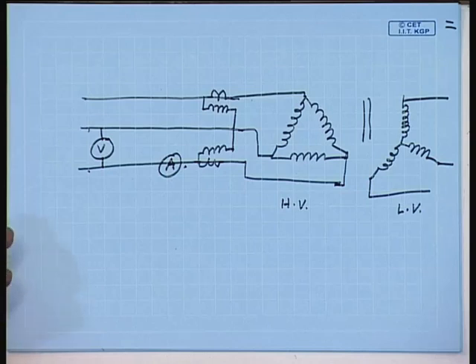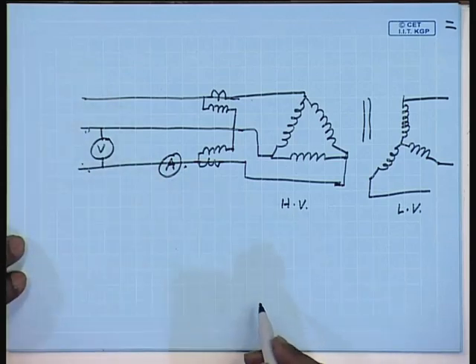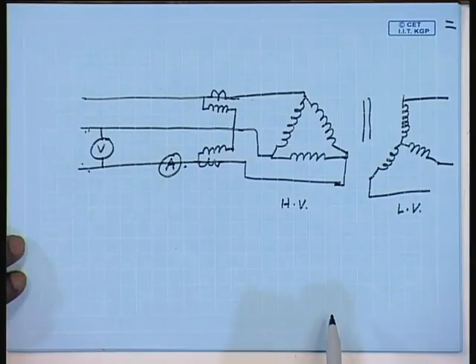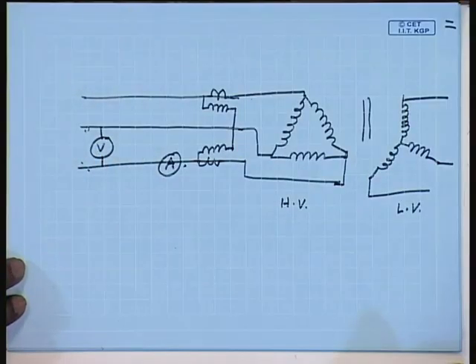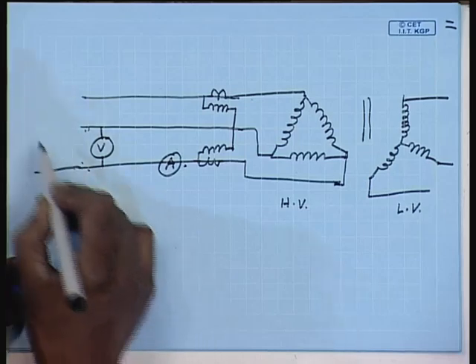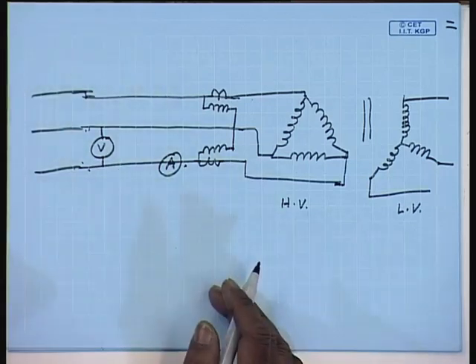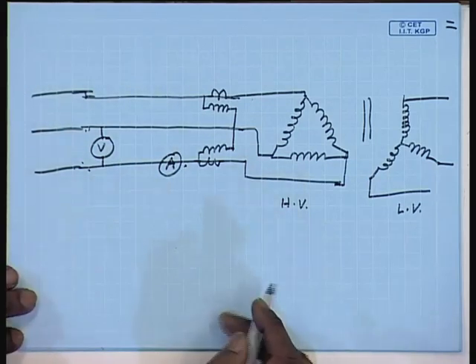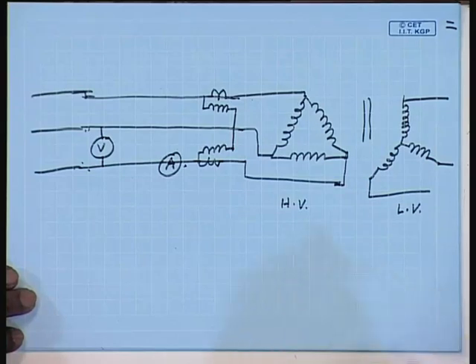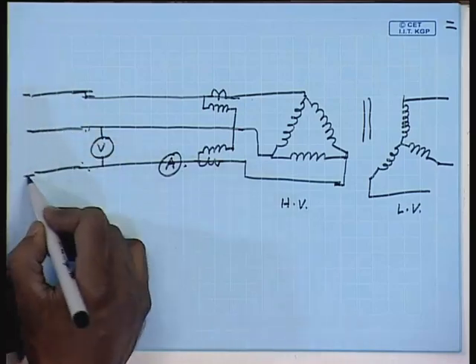However, in power transmission, this line voltage can be in excess of 200 kilovolt. This current can be in excess of several kiloamperes. So, instruments which can measure directly that kind of voltage or current are not available. Even if they are made available, working with them at such high voltages or currents is not desirable from the safety point of view. Hence, it is necessary to reduce these voltage and current magnitudes in order to bring them to the level where they can be safely measured, using again transformers. These are called instrument transformers.